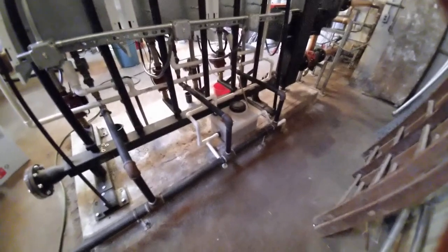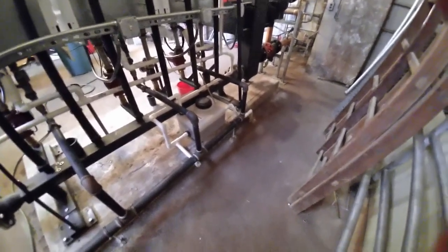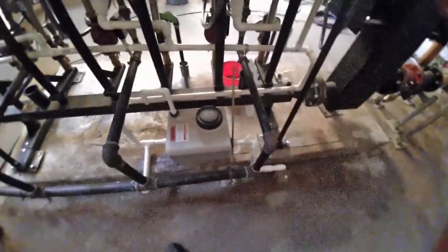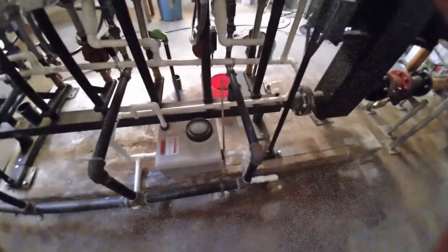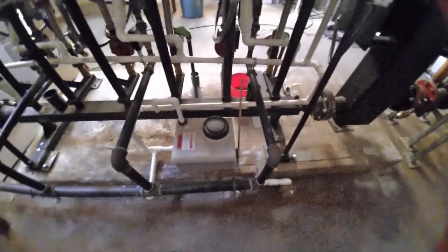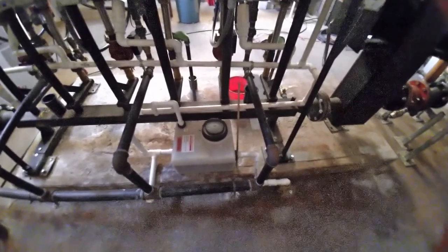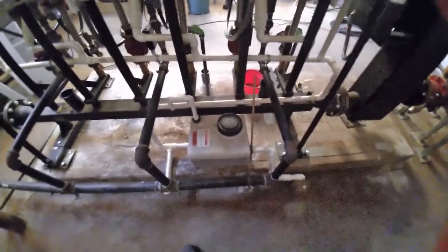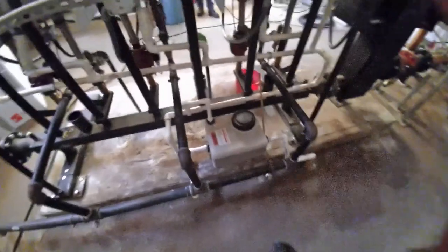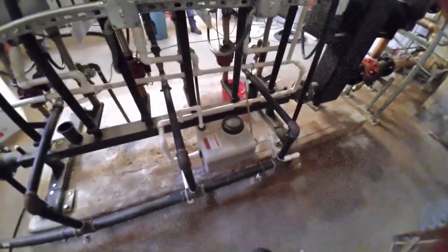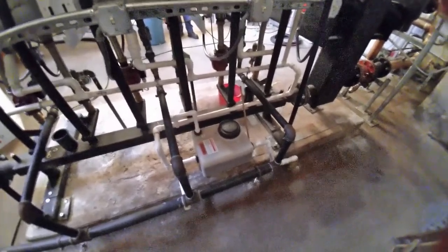One other important thing on these boilers, high efficiency units have condensate that comes out of them at a pH of about 3.8. So it's acidic condensate. You don't want to dump it down old floor drains and cast iron drain systems without having a neutralizer unit on it. So we always make sure that there's a properly sized neutralizer unit to take all the condensate from the full capacity of the boilers, and that needs to be checked annually too, to make sure that the neutralizer pellets in it aren't all neutralized and gone.